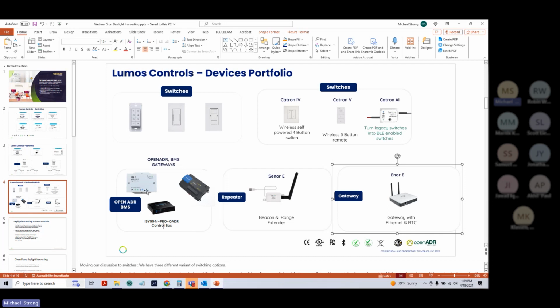So let's get started. Of course, we have our Open ADR BMS gateways, so we can connect to the Open ADR folks, meaning automatic demand response. That in the 2022 Title 24 Energy Code has become a requirement for buildings larger than 2,000 square feet. Power densities, they are requiring connections to an Open ADR. So they'll connect to the utility. The utility will be able to recommend off strategies during rolling brownouts, and they will give them control.